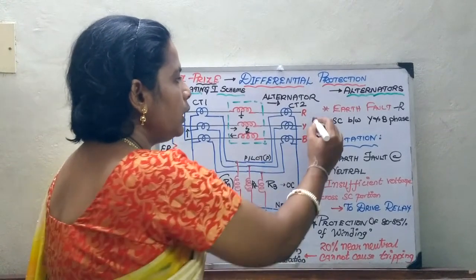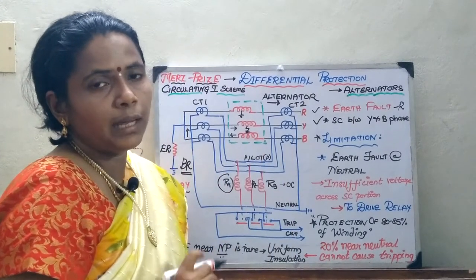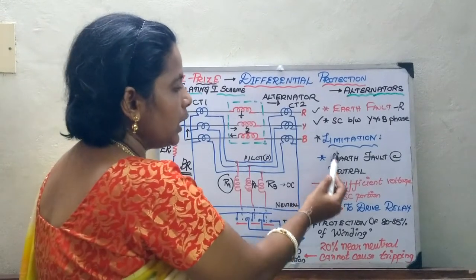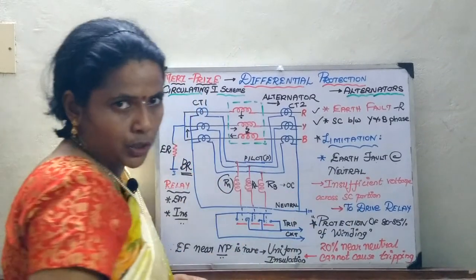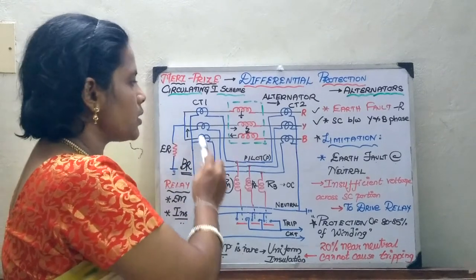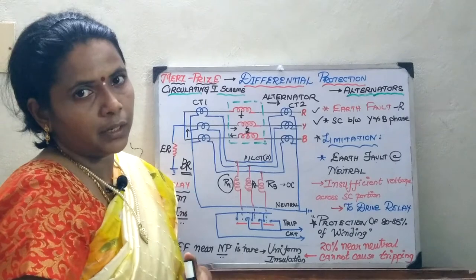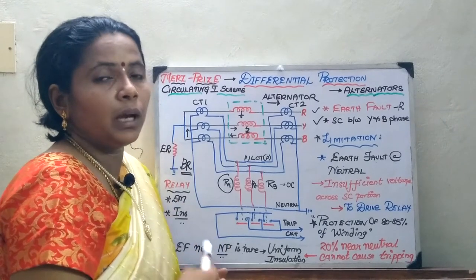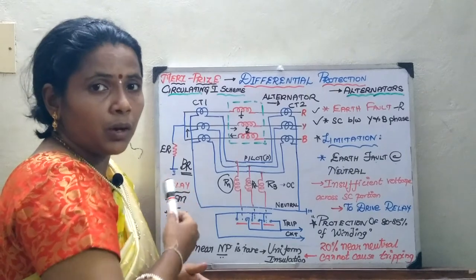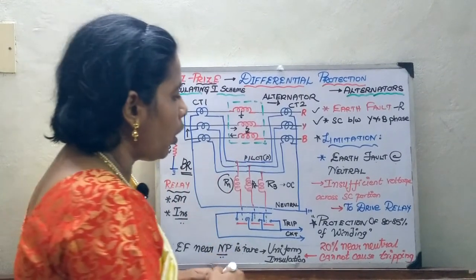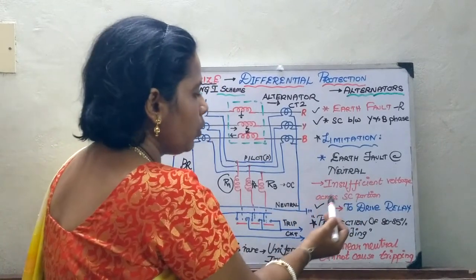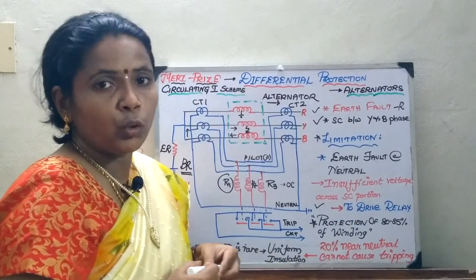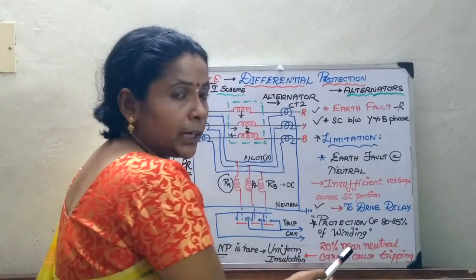We have seen the earth fault and phase-to-phase fault analysis. Now let us look at the limitation of this scheme. When an earth fault occurs near the neutral, it is observed that 100% protection of the stator windings cannot be achieved. If a fault occurs near the neutral, the magnitude of current develops insufficient voltage across the short-circuited portion, so the relay cannot operate immediately. Only 80 to 85% of the winding can be protected.